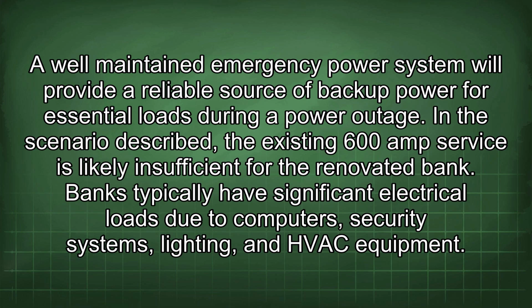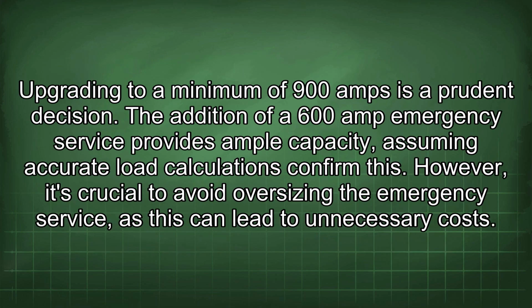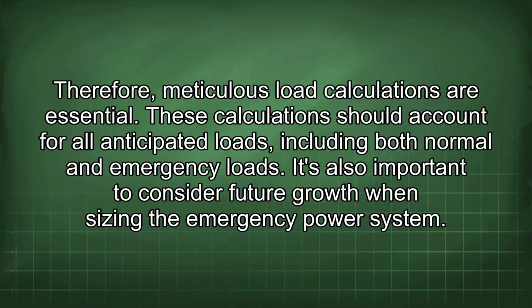In the scenario described, the existing 600 amp service is likely insufficient for the renovated bank. Banks typically have significant electrical loads due to computers, security systems, lighting, and HVAC equipment. Upgrading to a minimum of 900 amps is a prudent decision. The addition of a 600 amp emergency service provides ample capacity, assuming accurate load calculations confirm this. However, it's crucial to avoid oversizing the emergency service, as this can lead to unnecessary costs. Therefore, meticulous load calculations are essential.